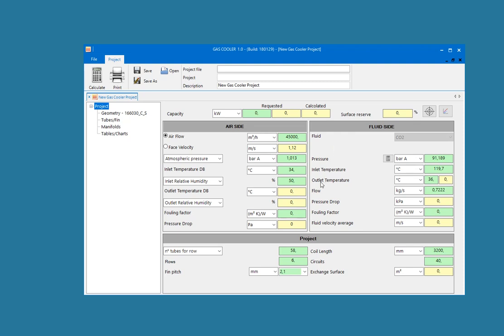Once you've inserted the inputs, the geometry, and edited the tube and fin materials and thickness, and if needed, the calculation of manifolds, you can proceed by clicking Calculate. The software will give you the capacity and the surface reserve percentage.